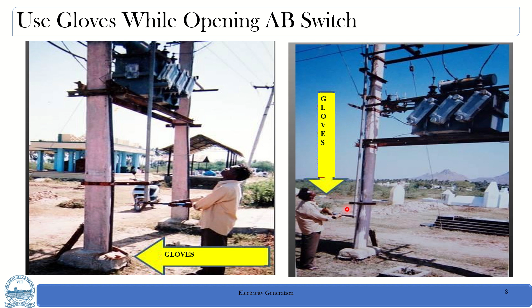While switching off the supply, it should be watched that all three blades are coming out uniformly. And while opening the air break switch, please ensure that the arc does not persist for a long time. Whenever you are separating two contacts, once the contacts are removed, the air in between the contacts becomes ionized because of the heavy current flowing through the conductor. As a result, a visible spark is produced across the two electrodes. This should not exist for a long time. A long-lasting spark between the electrodes says that there is a conduction, a conduction through the discharge between the two electrodes, which means the circuit is still live.